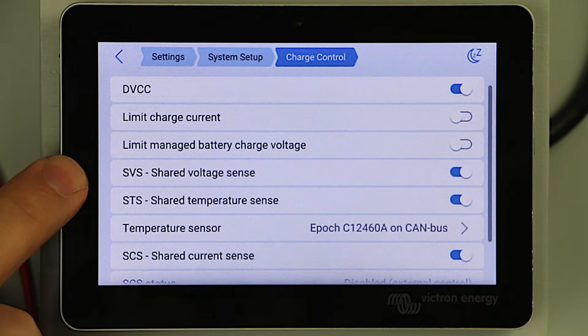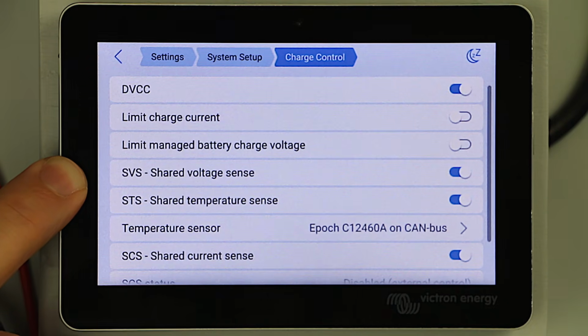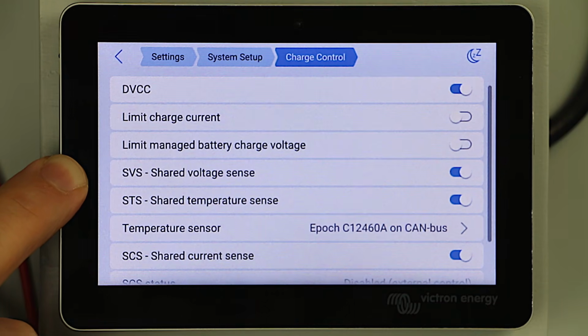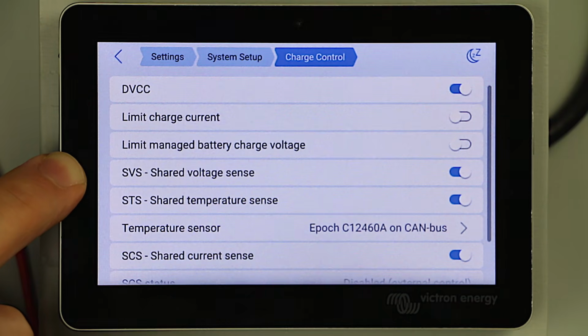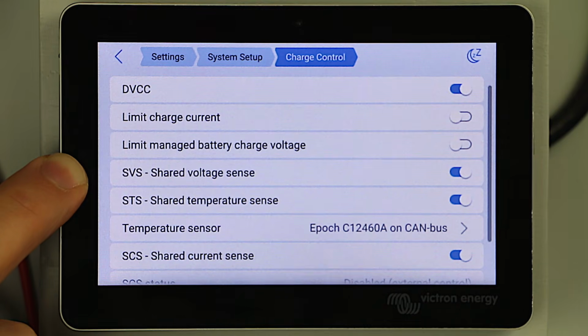On the shared voltage sense, it's also going to pull the voltage out of the batteries and share it with the chargers. When the chargers are putting out a high current and they're several feet away from the battery bank, they can't get an accurate assessment of the battery voltage, because the voltage drops between the charger and the battery bank—it drops every foot of cable you go down. With high current, the voltage reading at the charger gets distorted. So by sending the battery bank voltage to the chargers digitally, they get a much more accurate reading and can adjust accordingly.